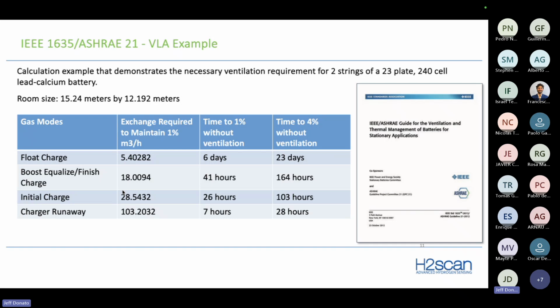They obviously had to go very tall on the battery racks just because it was such a small room. It was 3 tiers of vented lead acid batteries, and so they asked for an evaluation of how much air exchange they need to maintain below 1%, because the room was so small and they had quite a number of batteries inside the room.